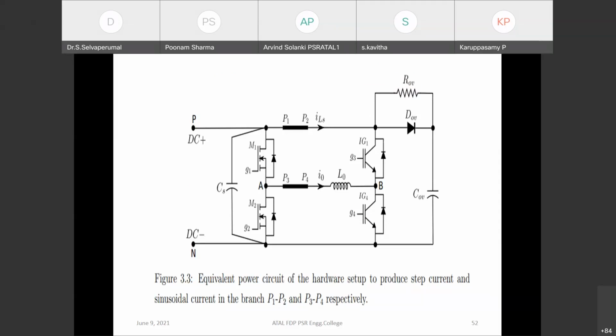So the hardware is configured in such a way that no modification is required to change over from sinusoidal current generation mode to step current generation mode or vice versa. The branches P1 to P2 and P3 to P4 are screw mounted and can be detached to accommodate the current sensor under test.